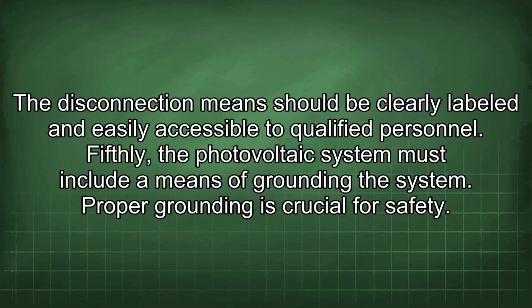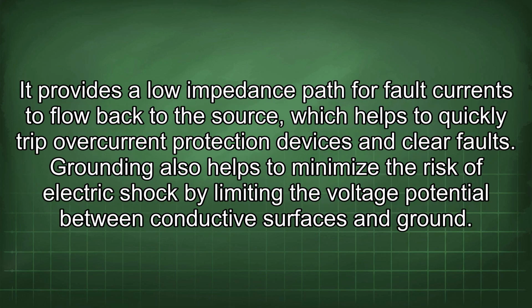Fifthly, the photovoltaic system must include a means of grounding the system. Proper grounding is crucial for safety. It provides a low impedance path for fault currents to flow back to the source, which helps to quickly trip overcurrent protection devices and clear faults. Grounding also helps to minimize the risk of electric shock by limiting the voltage potential between conductive surfaces and ground.